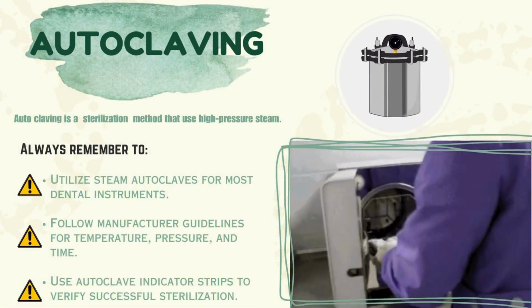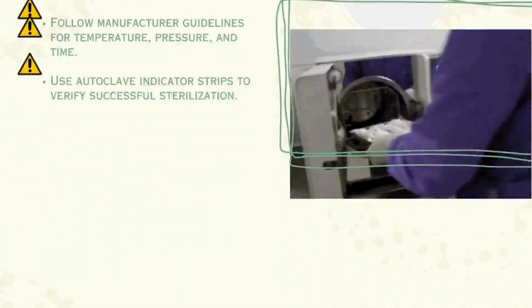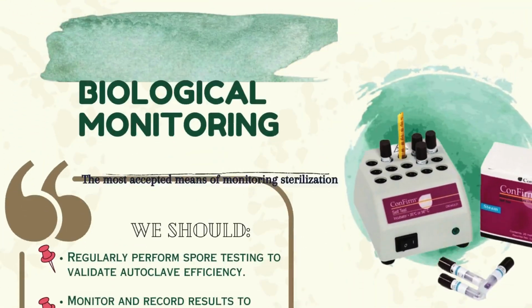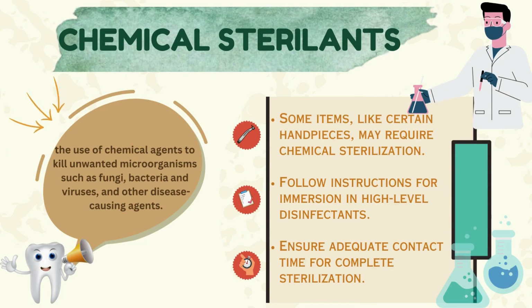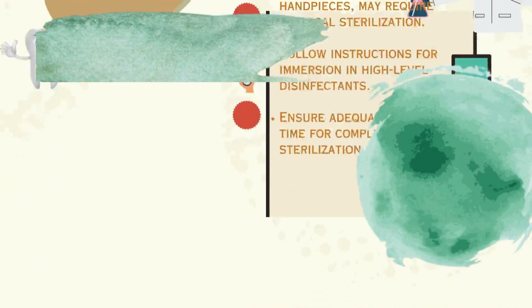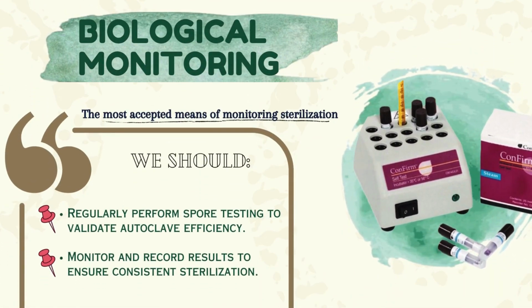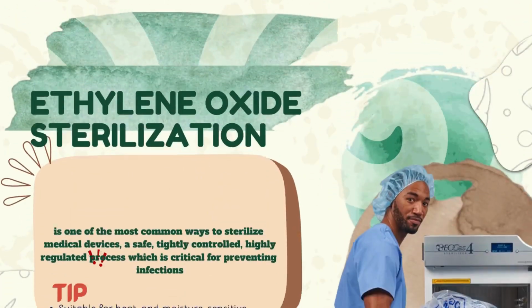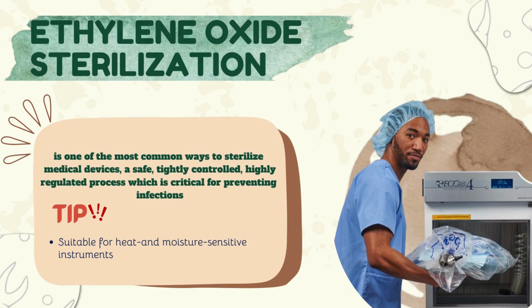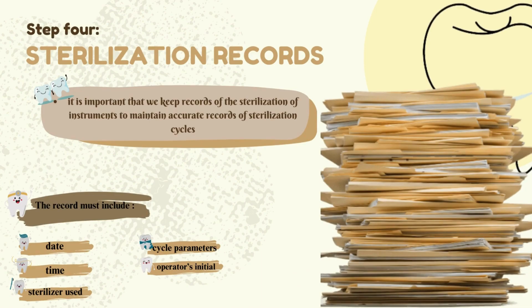First, autoclaving. Utilize steam autoclaves for most dental instruments. There are also chemical sterilants and biological monitoring. In chemical sterilants, some items, like certain handpieces, may require chemical sterilization. For biological monitoring, regularly perform spore testing to validate autoclave efficiency. Lastly, there is ethylene oxide sterilization. This is suitable for heat and moisture-sensitive instruments and should be performed in a designated area adhering to strict safety protocols.